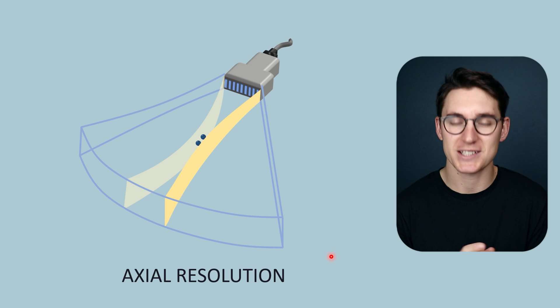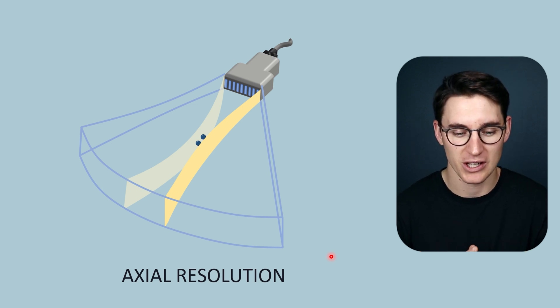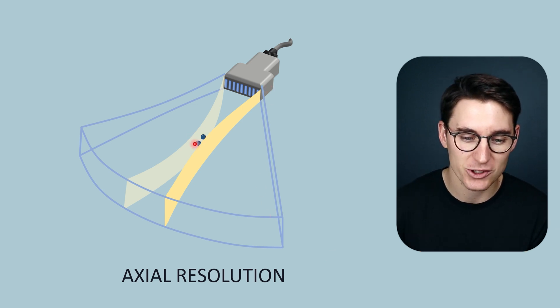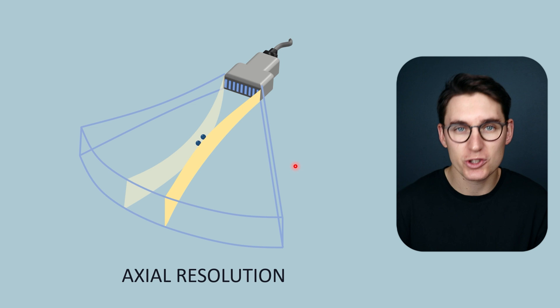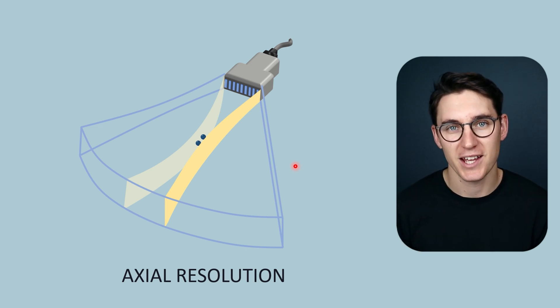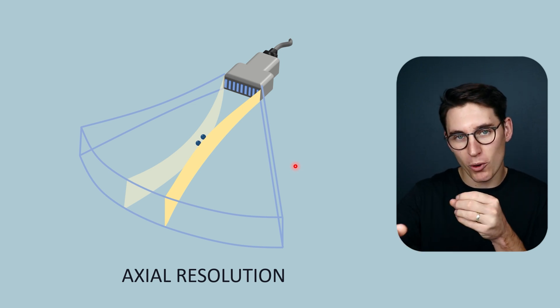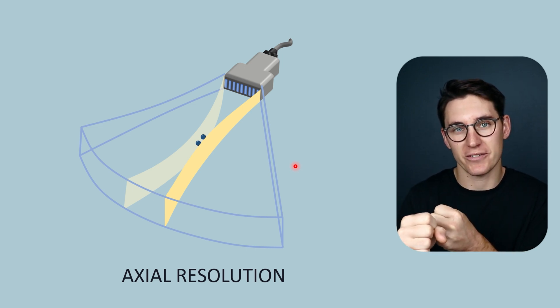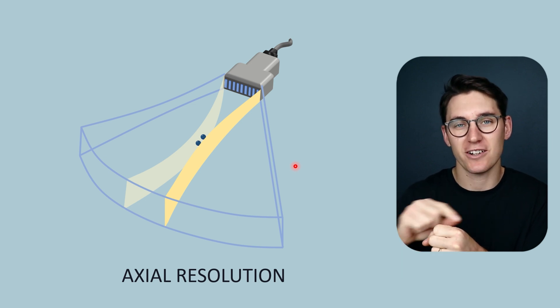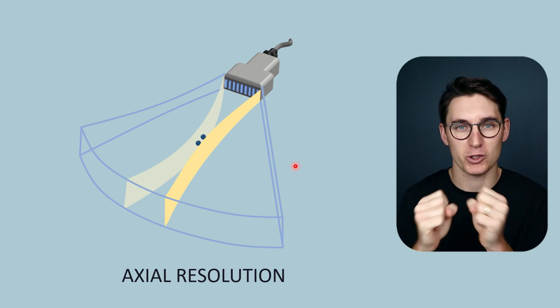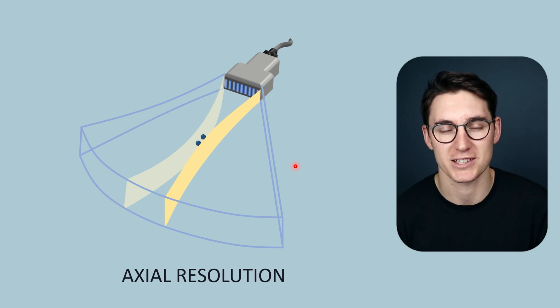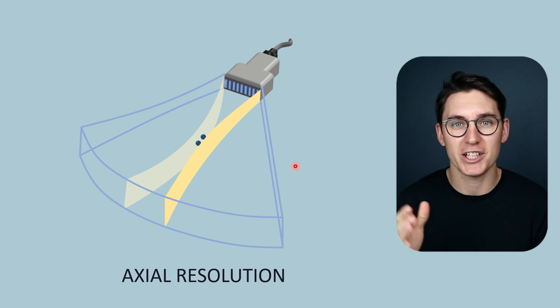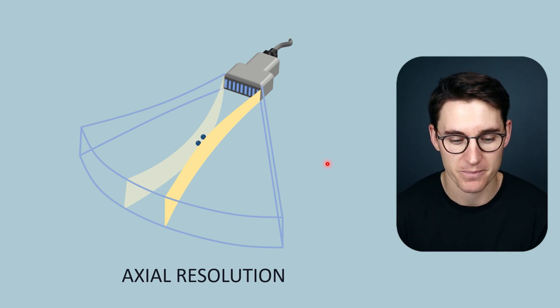So what exactly is axial resolution? Axial resolution is the ability to differentiate two objects at varying depths. There will be a point where those two objects are close enough that the ultrasound machine can't tell that there's a gap between them. Once that happens, we have reached our axial resolution limit.